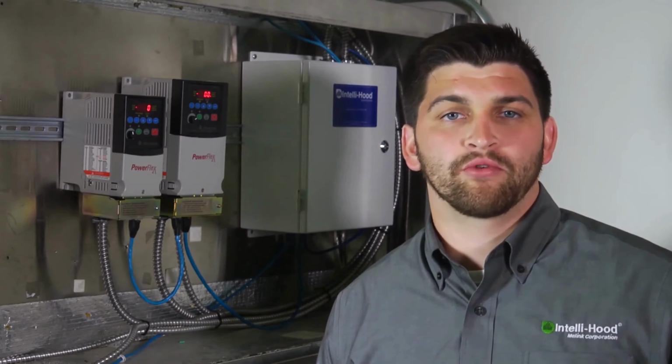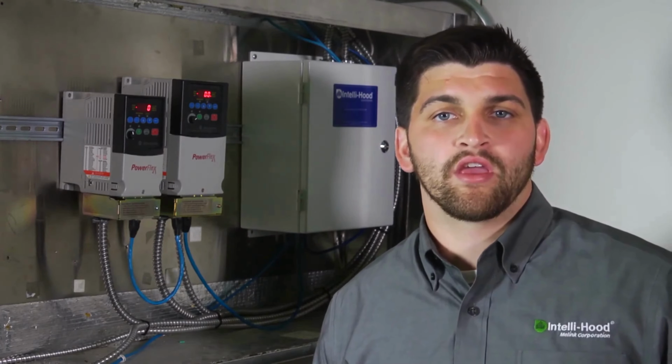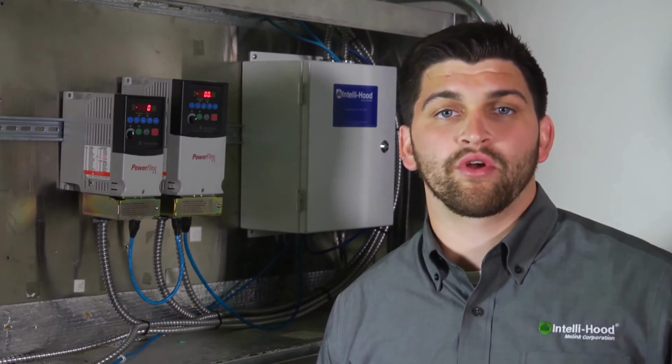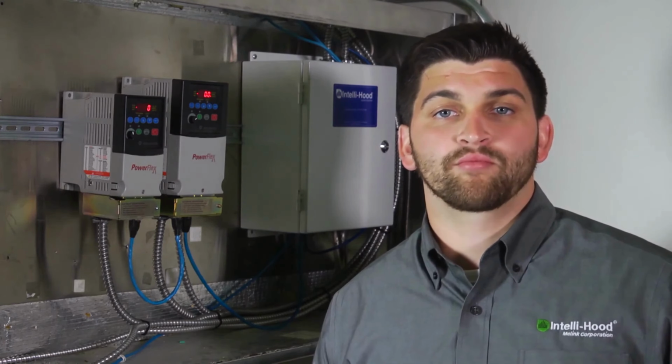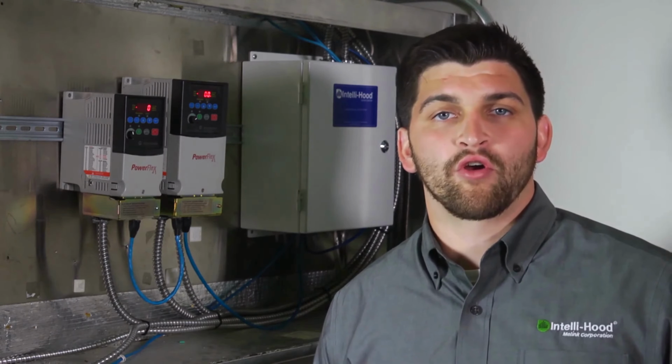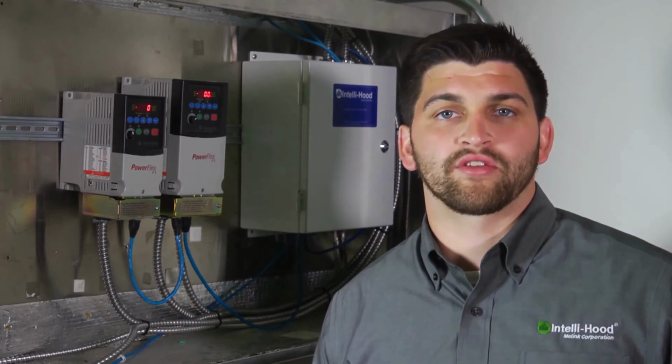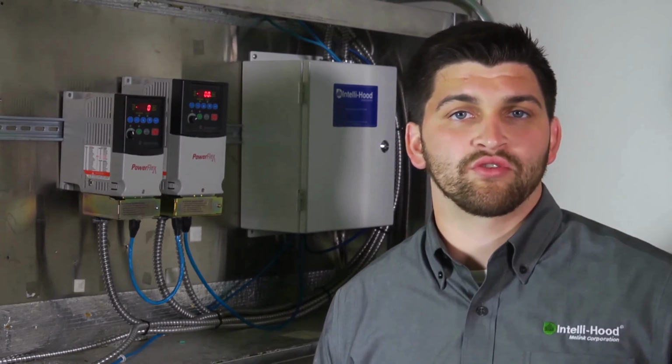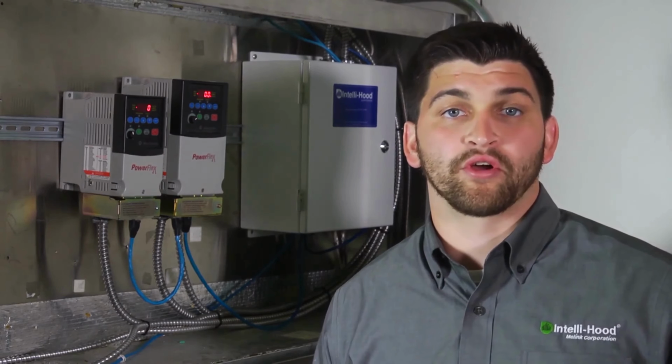The following are examples of advanced troubleshooting you may be able to perform on-site. If, however, you are uncomfortable working with electrical equipment, contact Melink Technical Support or your local licensed electrician. For overvoltage faults, check for water at the disconnect. Adjusting the deceleration scale on the VFD may help this issue from the motor regeneration on the bus voltage.